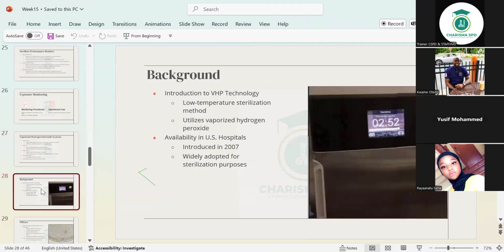And when we talk about the parameters, don't be confused. You see the screen that you see there on the picture? The parameters are going to be written there. It's about the temperature, the exposure time, and then the dry time. Those are the parameters. They are like measurements. All right? So they keep talking of parameters. Everything with meters on it tells you it's a measurement. It's a measurement of something. So the parameters for this, as we keep talking, is the temperature, the exposure time, which is the diffusion time or the penetration, and then the dry time. Okay? And that's all. So based on that, you select what you're doing and what instrument you are cooking or sterilizing, and then use that.